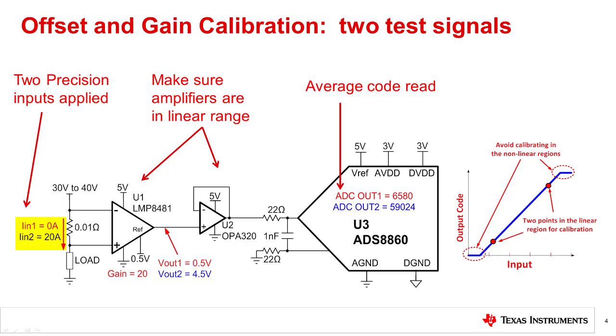In this example, we apply 0 amps and 20 amps and measure the associated output codes. Note that 0 amps drives the output of U1 to 0.5 volts, and 20 amps drives the output to 4.5 volts. So these test signals keep the system in the linear range. It is very important that the test signals used are very accurate. Any error in the test signal will introduce error in the calibration coefficients and minimize the effectiveness of the calibration.